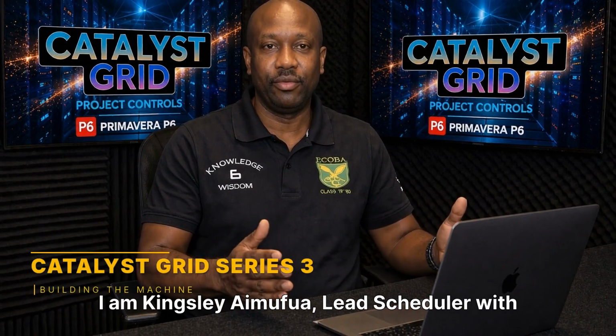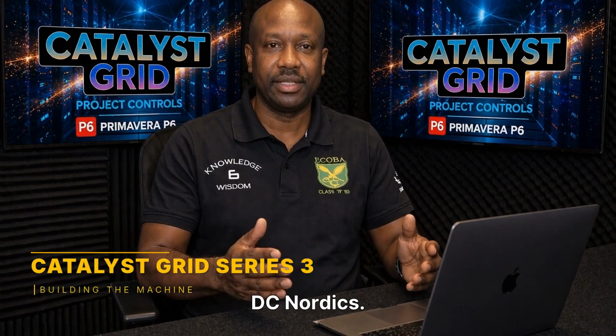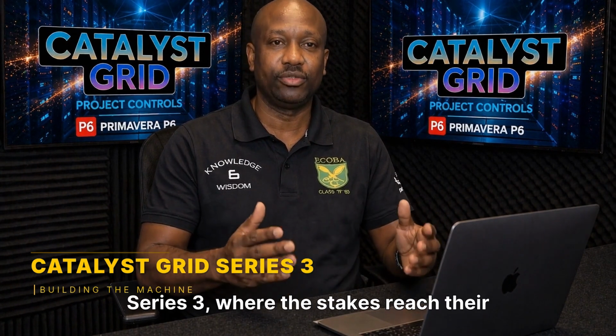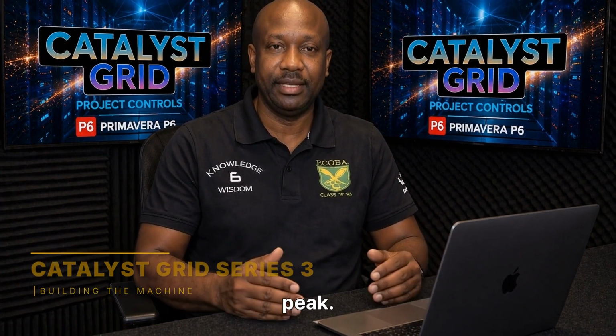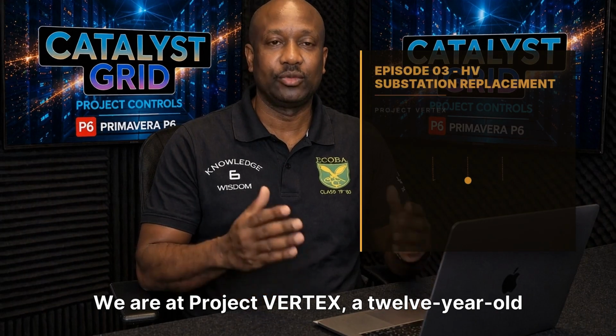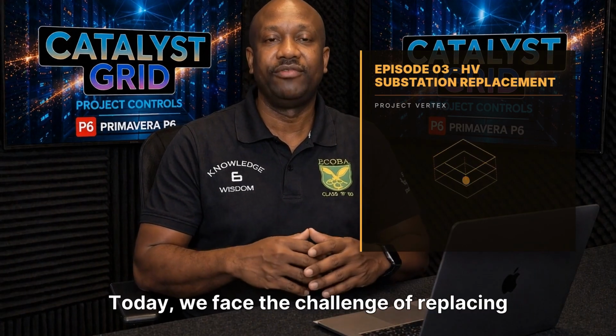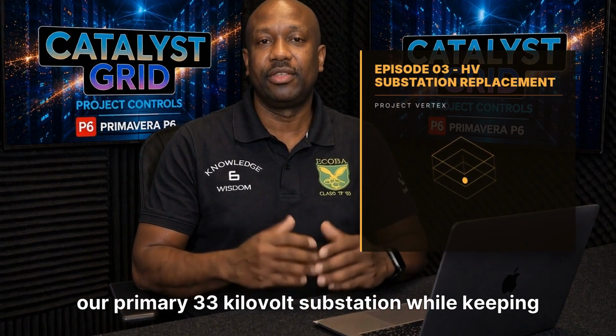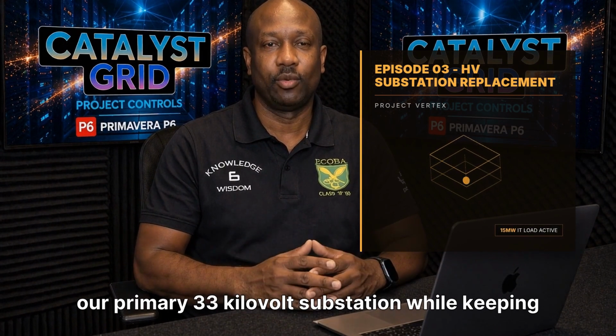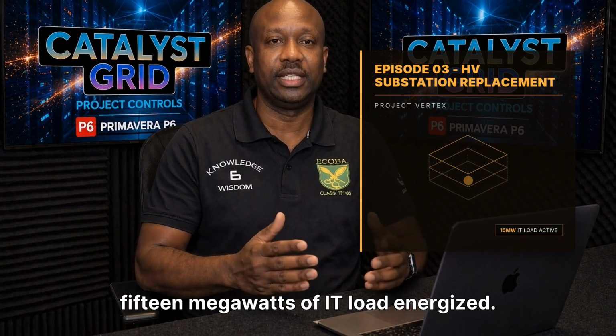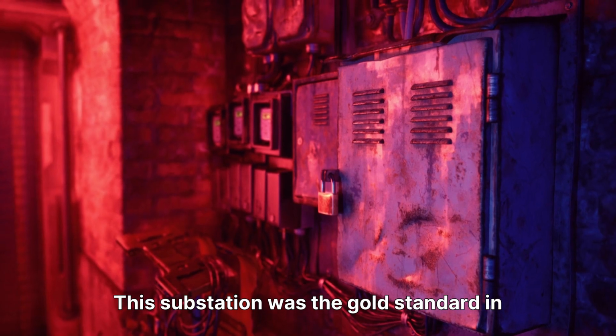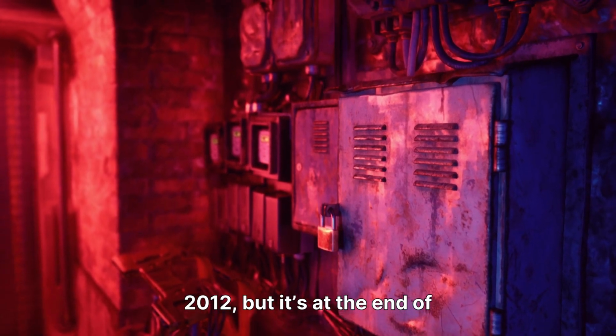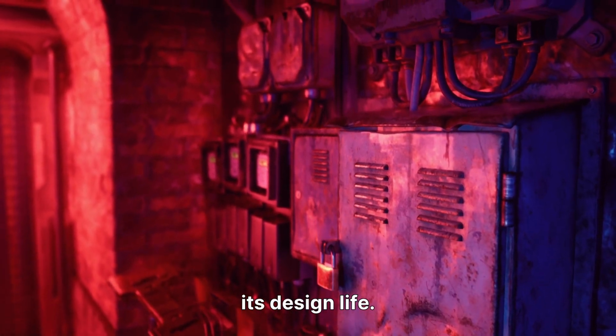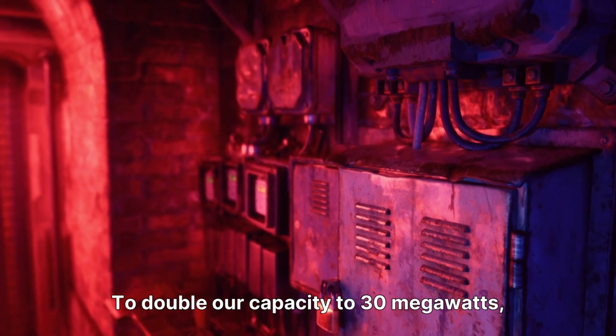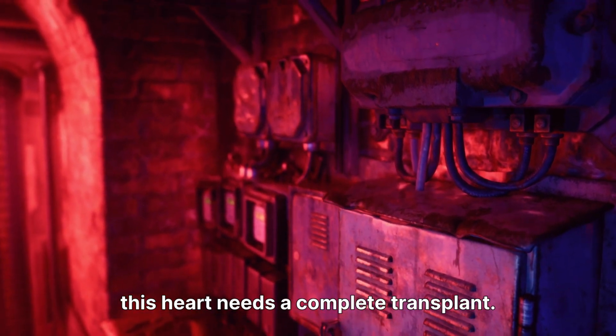I am Kingsley Imufua, lead scheduler with DC Nordics. We are moving into the heart of Series 3, where the stakes reach their peak. We are at Project VERTEX, a 12-year-old facility. Today, we face the challenge of replacing our primary 33 kilovolt substation while keeping 15 megawatts of IT load energized. This substation was the gold standard in 2012, but it's at the end of its design life. To double our capacity to 30 megawatts, this heart needs a complete transplant.